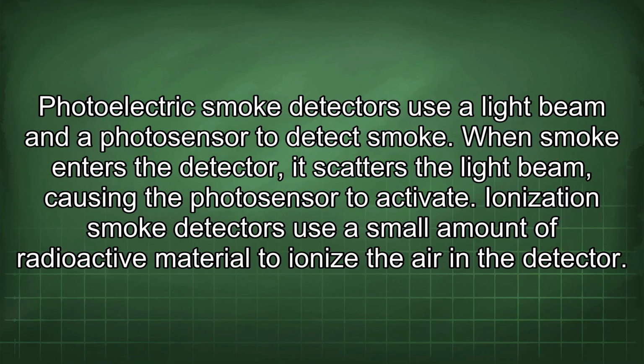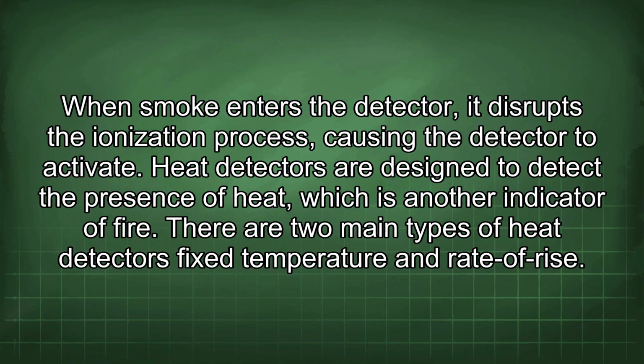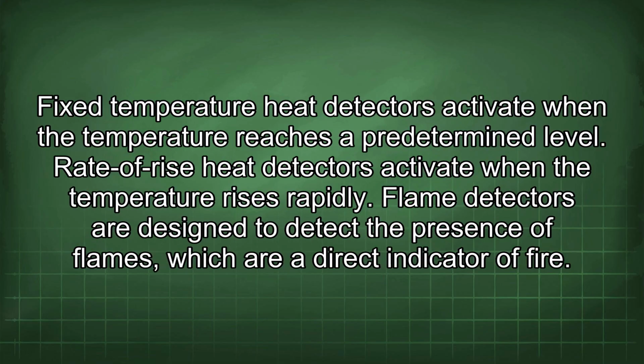Ionization smoke detectors use a small amount of radioactive material to ionize the air in the detector. When smoke enters the detector, it disrupts the ionization process, causing the detector to activate. Heat detectors are designed to detect the presence of heat, which is another indicator of fire. There are 2 main types of heat detectors: fixed temperature and rate of rise. Fixed temperature heat detectors activate when the temperature reaches a predetermined level. Rate of rise heat detectors activate when the temperature rises rapidly.